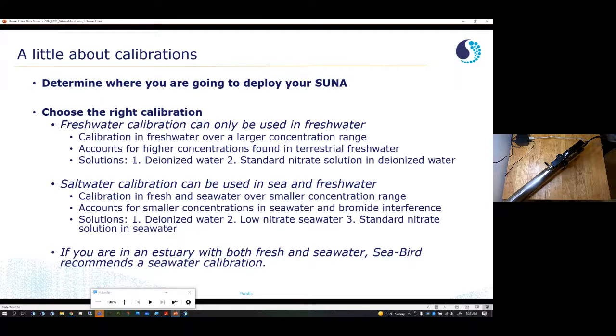and then we use a standard nitrate solution in deionized water to understand that calibration range. A saltwater calibration is a little bit more flexible. It can be used in both seawater and freshwater. It does calibrate over a somewhat smaller concentration range, because the expectation is that in the ocean nitrate concentrations are pretty low. It also accounts for bromide interference. So we actually do three calibrations here. The first one is the same: deionized water, so water with nothing in it. We do a low nitrate seawater to get the low range, and then a standard nitrate solution, but this time in seawater. From that, we can calculate the bromide interference. If you're in an estuary, and a lot of people use these really close to the coast, you're going to see both fresh and seawater. We recommend that you use the seawater calibration because it will cover both.